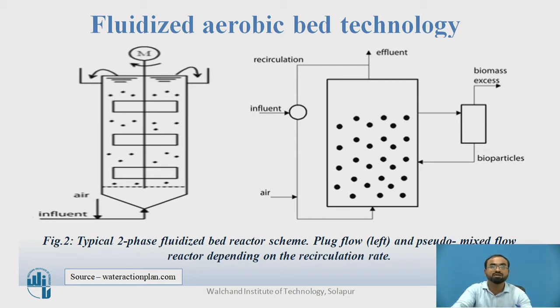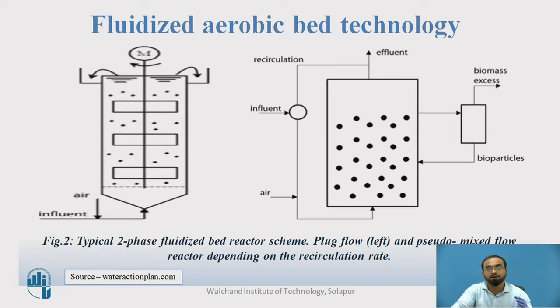If air is included and a three-phase system is made, automatically the air will cause the biomass to hit each other, and whatever layer of microorganisms has formed on the media will automatically detach and get settled at the bottom, decreasing the MLSS concentration. Therefore, the two-phase system is a good system. If MLSS increases, some part of the biomass or bioparticles are taken out, cleared up, and added back in, so the MLSS is easily maintained.